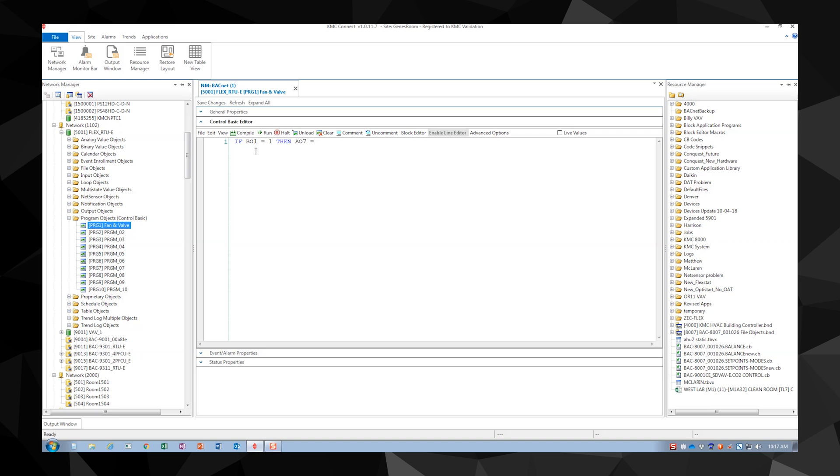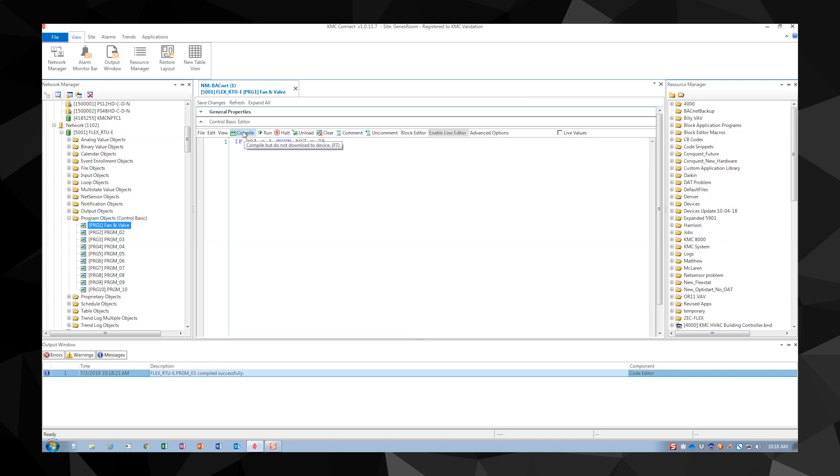Our first statement will read if B01 equals 1 then A07 equals 25. In this case if B01 is on then A07 will modulate to 25%. Compile or run the program to see if it works correctly.